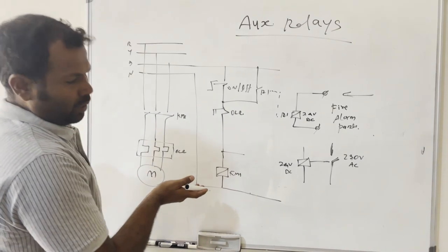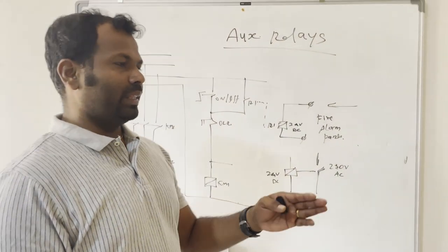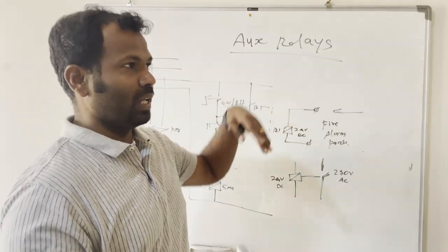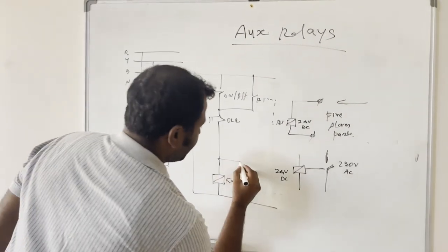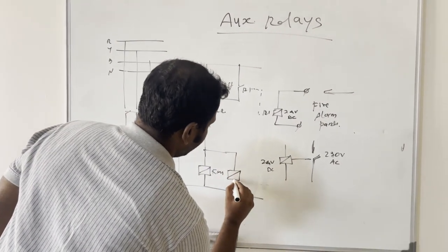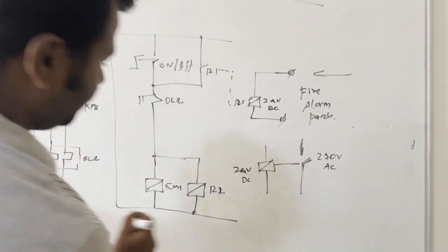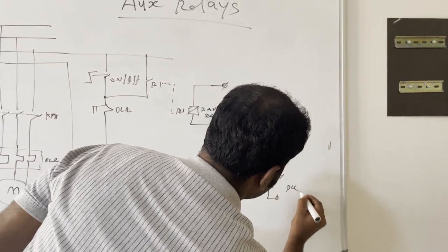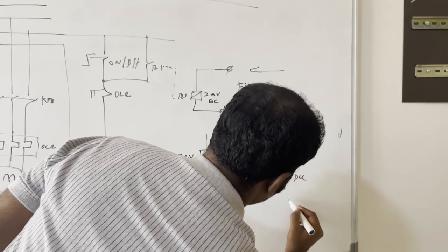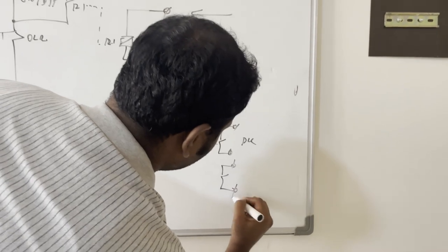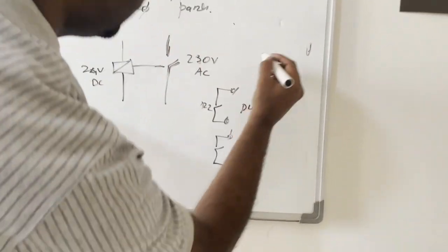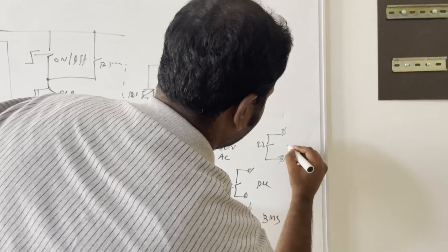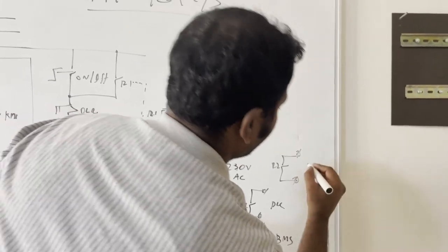You can also multiply signals. If you have only one contactor without any auxiliary NO/NC contacts but want to send the running status to different places — one PLC, one SCADA, one BMS, or other remote monitoring areas — you can add one auxiliary relay R2, and from R2 you can give signals to PLC, BMS, and any other remote monitoring area.